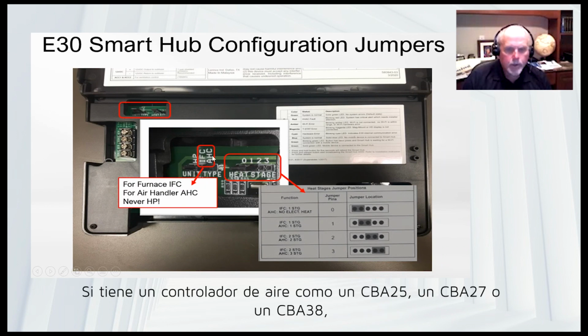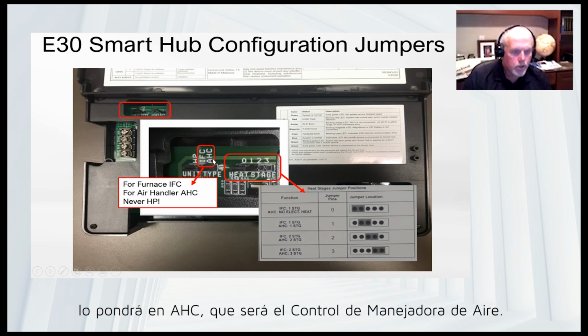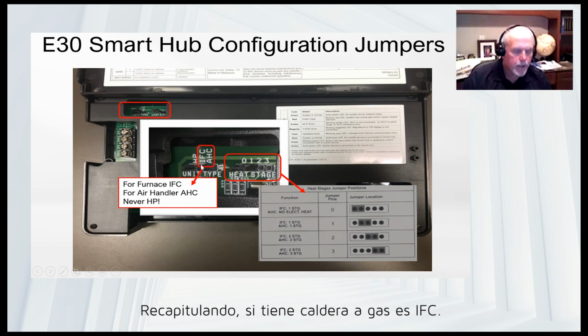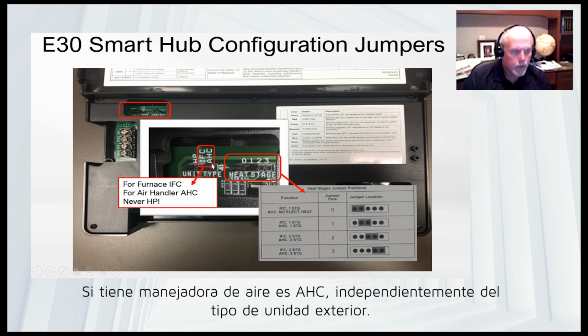If you have an air handler, such as a CBA 25 or a CBA 27 or a CBA 38, you will put it on AHC, which will be air handler control. That's what it stands for, air handler control. So to make it easy, if you have a gas furnace, it's IFC. If there's an air handler, AHC, regardless of what the outdoor unit is.